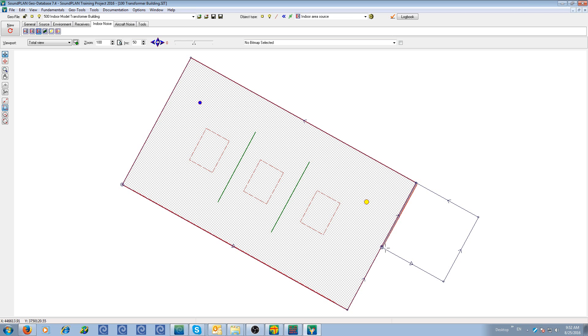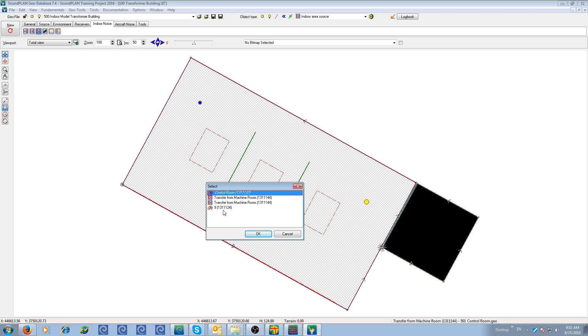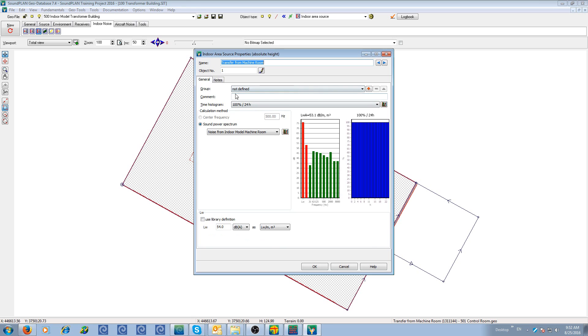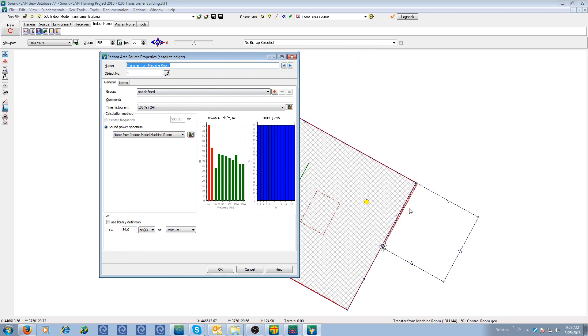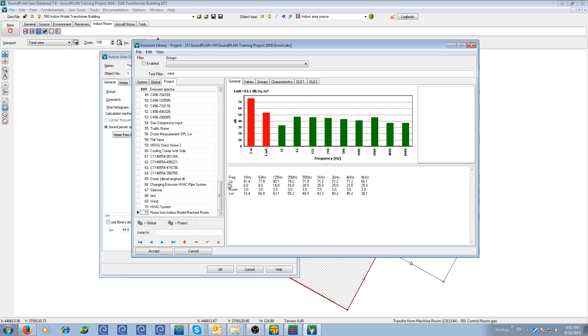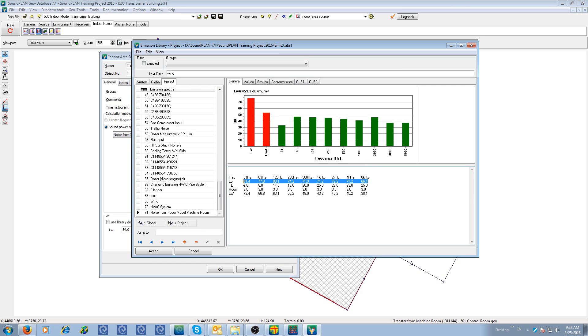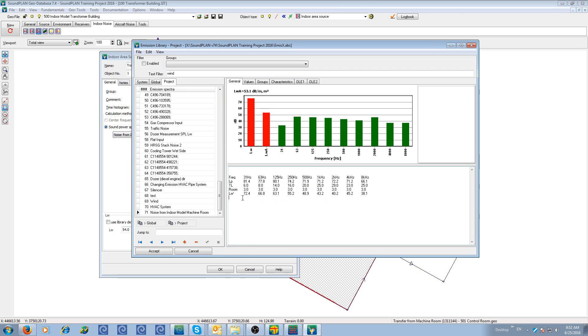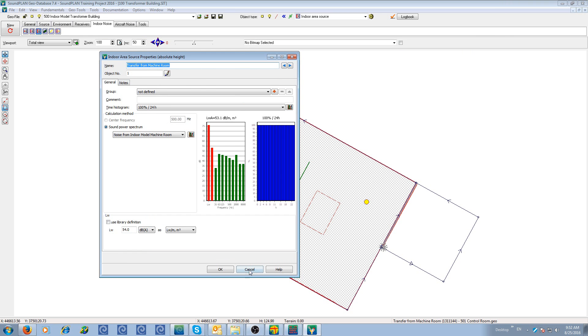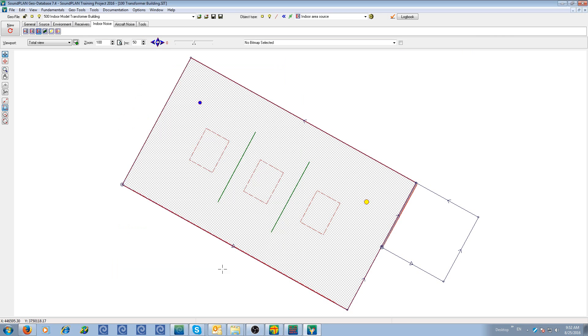Then in terms of the second room here, the control room, we have a second building, defined with the absorption and so forth. And then here we have also an indoor area source. This indoor area source is using the interior model that we will have later for this room. And we subtract the sound transmission. So here I have already done that. This is the spectrum. This is the interior level that we'll get for the other room. We have the transmission loss, the correction. And then we have the intensity level on the side of the control room radiating into this control room.